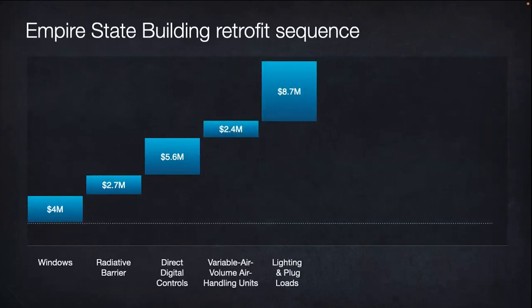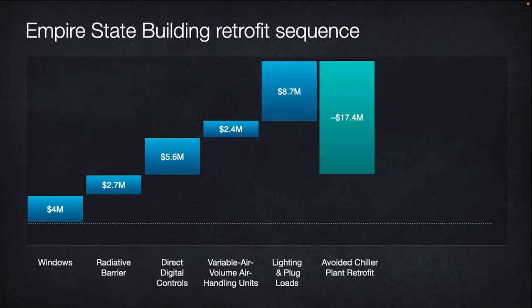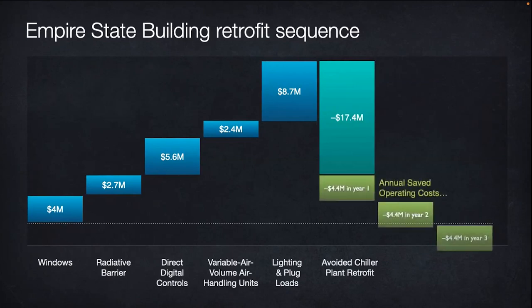But then renovating smaller chillers instead of adding bigger chillers saved about $17 million of CapEx, paying for most of the other improvements and cutting the payback to 3 years, or less than 1 year if we had counted non-energy benefits to the owner or tenants. A major ESCO didn't get the job because they offered a 3-year payback with disintegrated design, yielding only a sixth the savings we got.